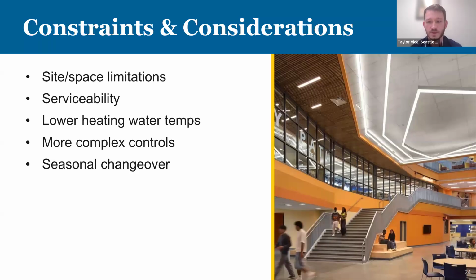We're looking at some situations here at SPS where we want to get rid of our gas boilers and put in heat pumps, but the building is designed with loop temperatures much warmer than we could produce with a heat pump. So what are the options there? Some things to consider—it's not always a like-for-like or one-for-one replacement.